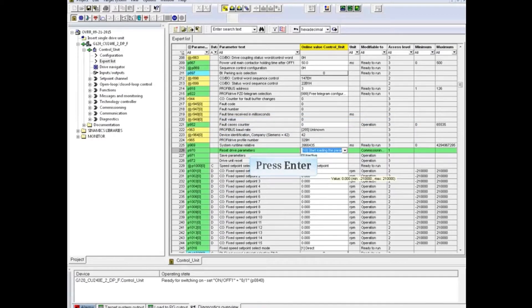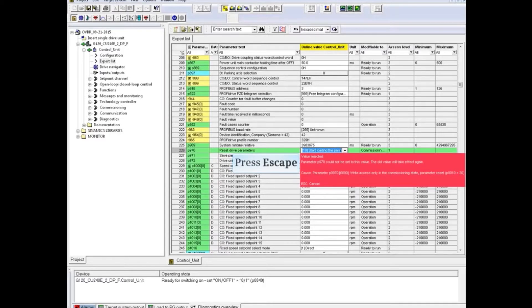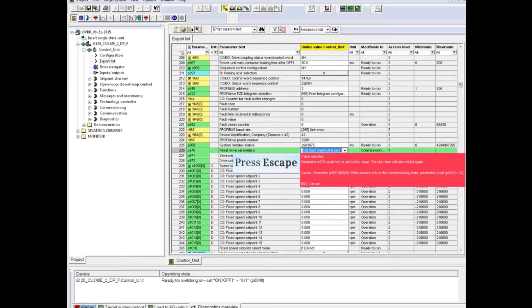Press the Enter key. In this example, the drive is not in the proper mode for modification of this parameter. The drive must be in Commissioning mode. Press Escape to clear this warning.